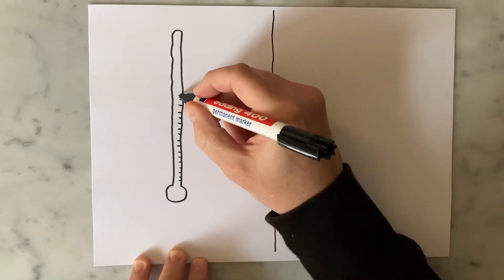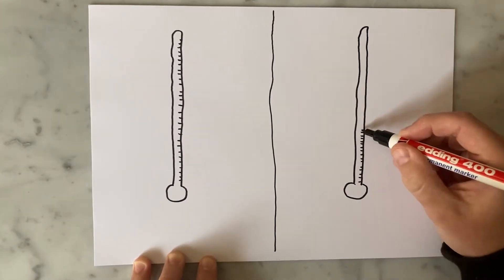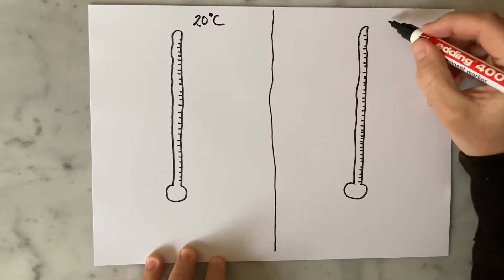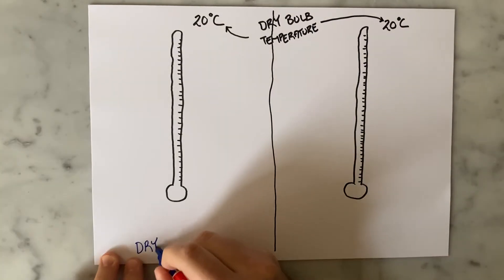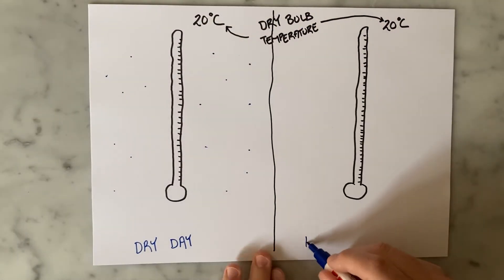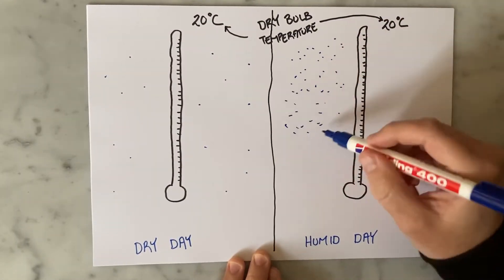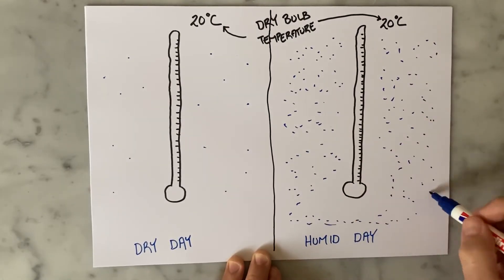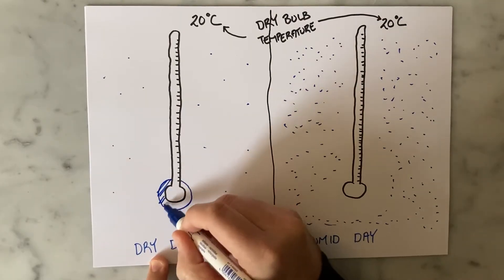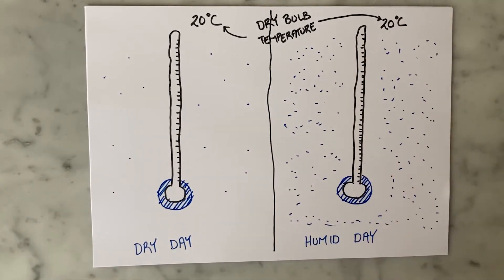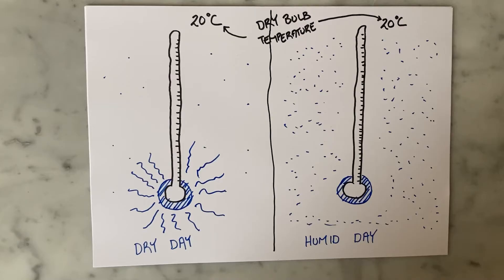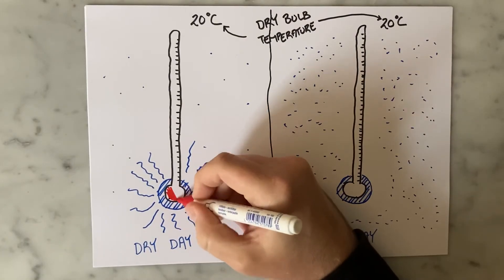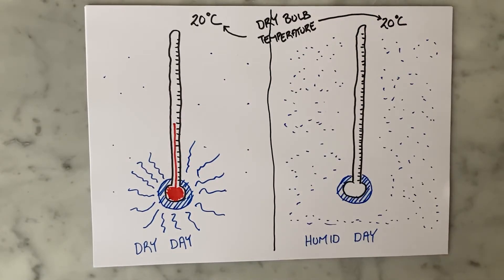Let's consider what happens in two scenarios. Take two thermometers, both reading 20 degrees dry bulb temperature. One is measuring temperature on a very dry day with little moisture in the air, while the other is measuring 20 degrees on a very humid, sweaty, clammy day. Now wrap both thermometer bulbs with a wet cloth — the wick. On the dry day, the rate of evaporation is very high because there is plenty of space in the air for water to escape into. The more water escapes, the more energy it steals from the thermometer, so the reading drops very low.